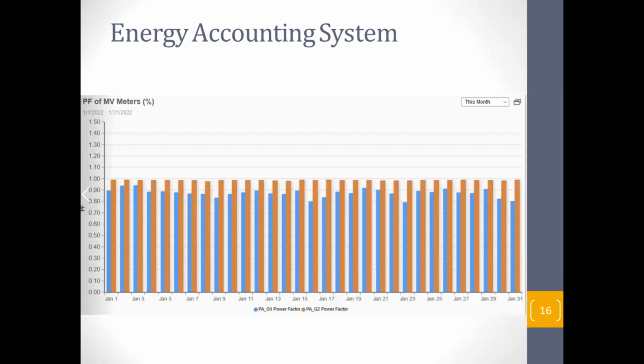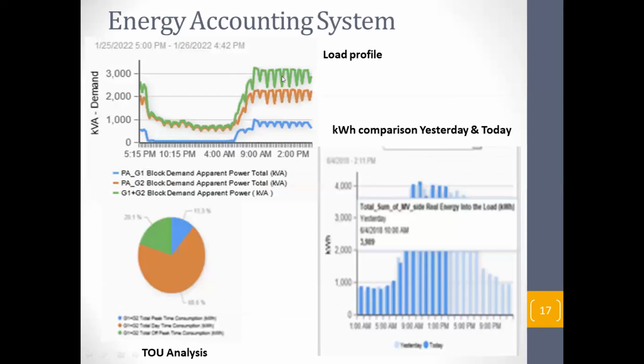The power factor banks are all in the low voltage system, but you can monitor the power factor. You can see in one feeder, power factor is quite stable. The other one is varying. This is about 0.98, the other one is about 0.9, because the second feeder is connected to many induction equipment, even elevators and all that. So the load is varying. So all these you can read. And this is the load pattern. And this is the time of use analysis.